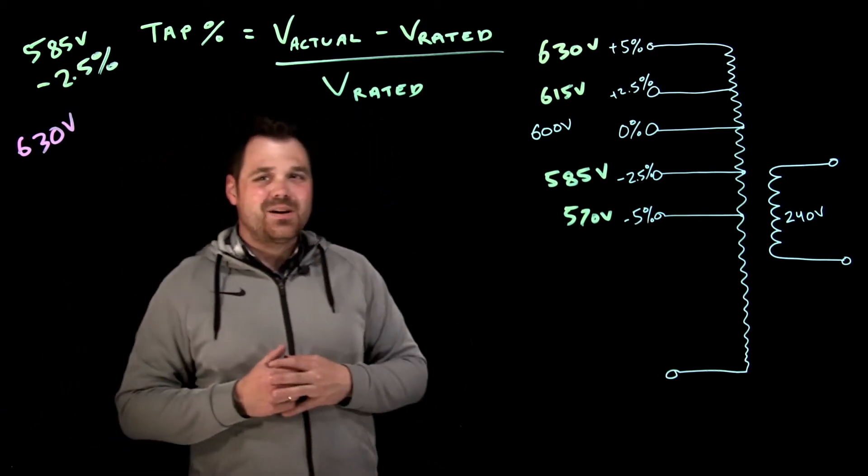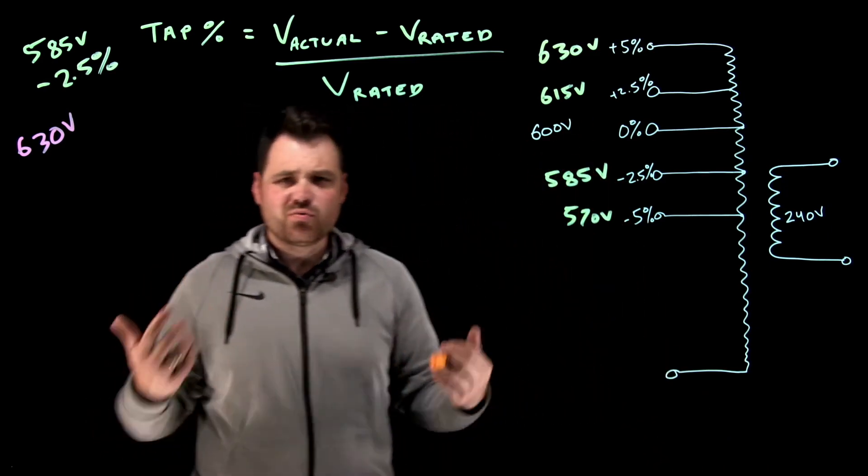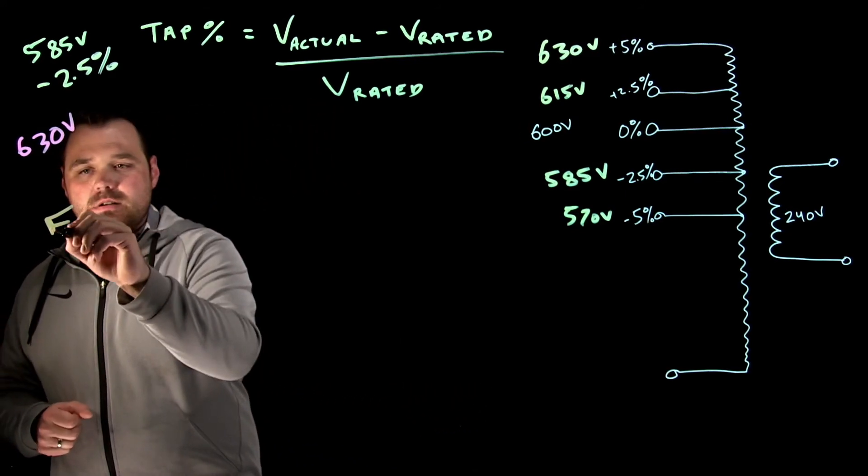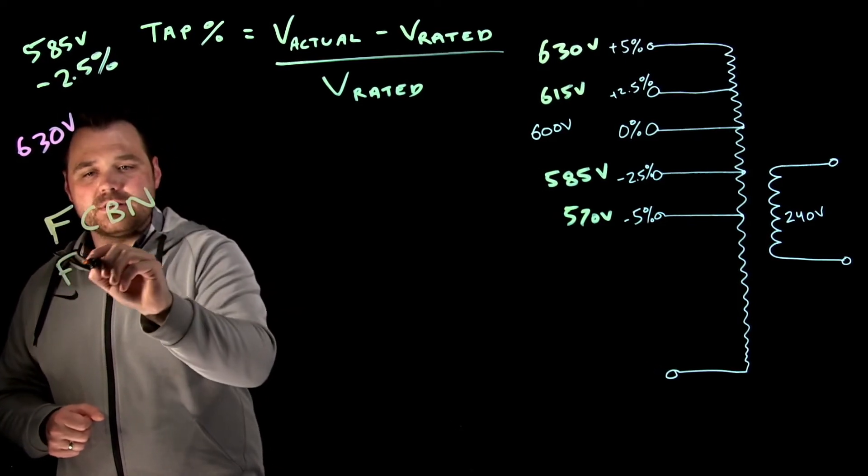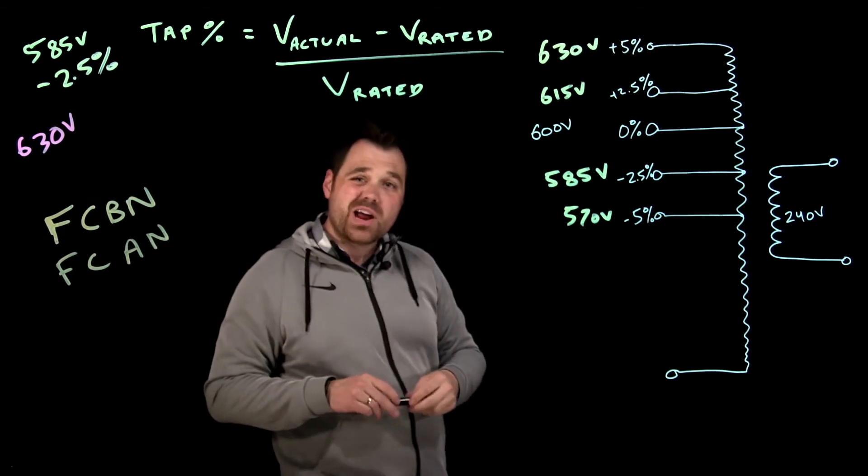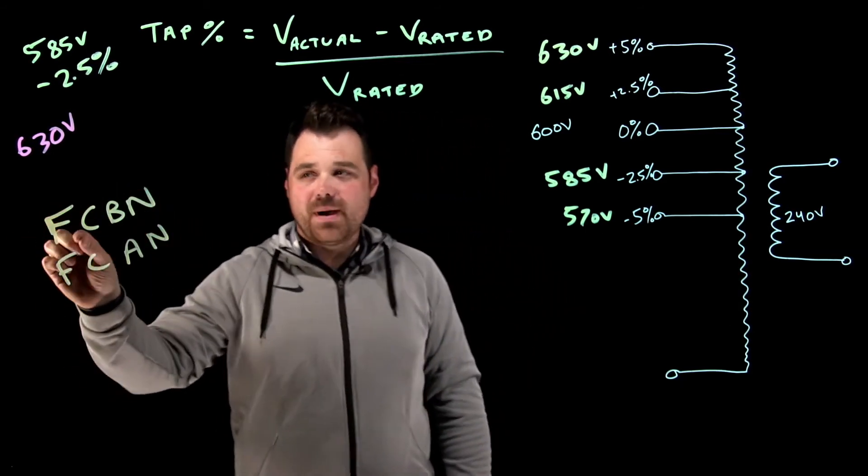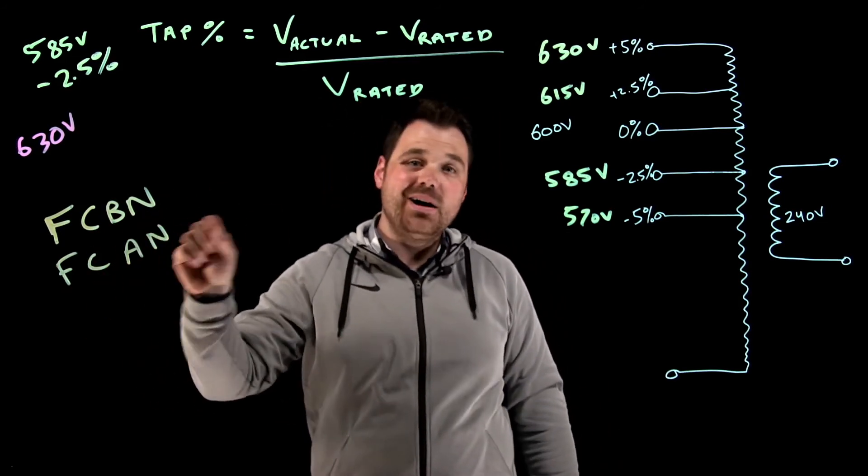But the last thing I want to talk about is a rating of these taps. So on these taps, there's actually going to be a rating. You'll see things you might see FCBN or FCAN. So those ratings will be right on the taps. Now what that stands for is full capacity below normal or full capacity above normal.